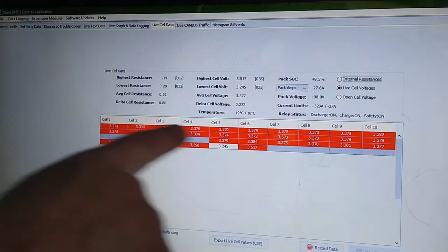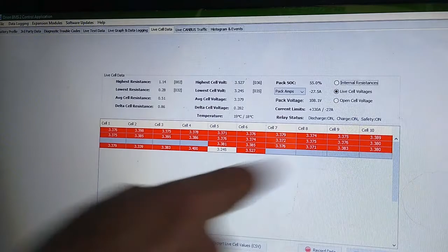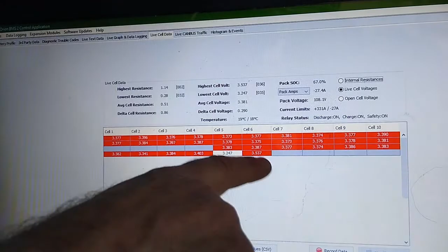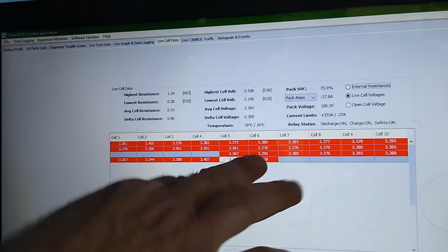The way the system works is it will charge the batteries until at least one of these cells reaches 3.65 volts. Once one of those cells reaches 3.65 volts, it'll stop charging. Now the problem is one of them has already reached 3.5, and that's when it starts to balance the batteries. You can see it already thinks it's at 70% state of charge, because the batteries are so far out of balance here.